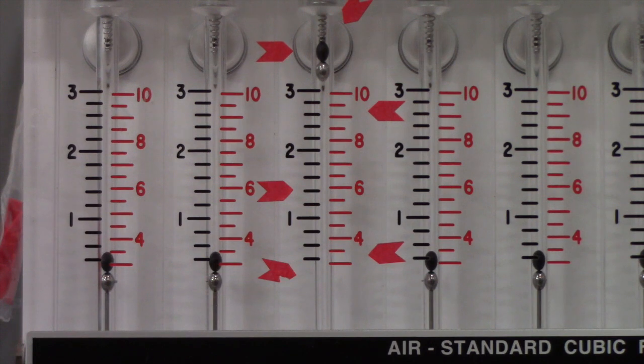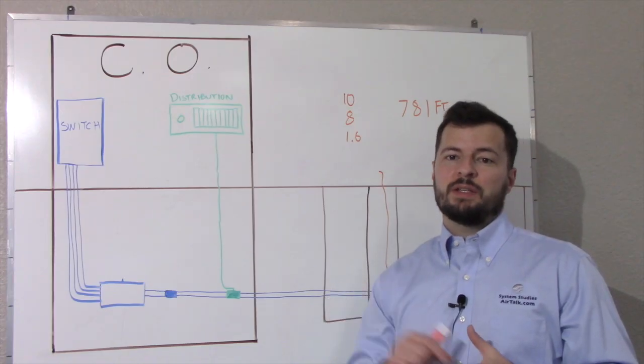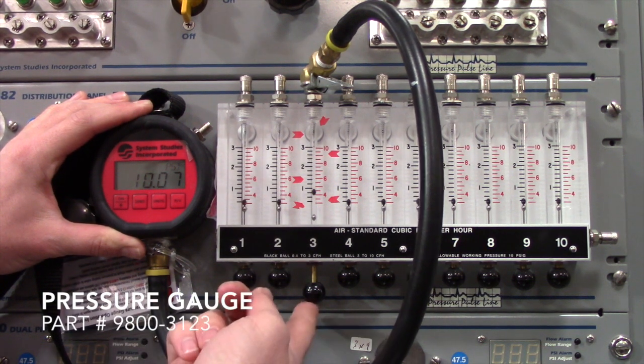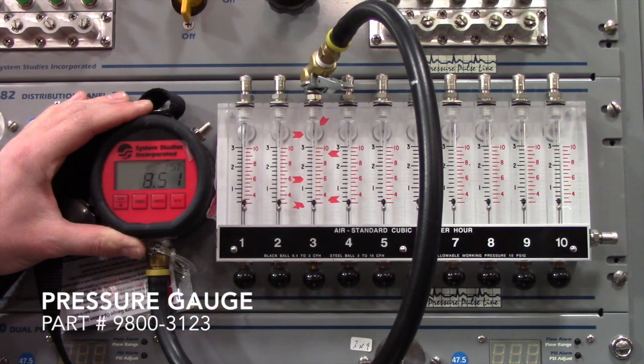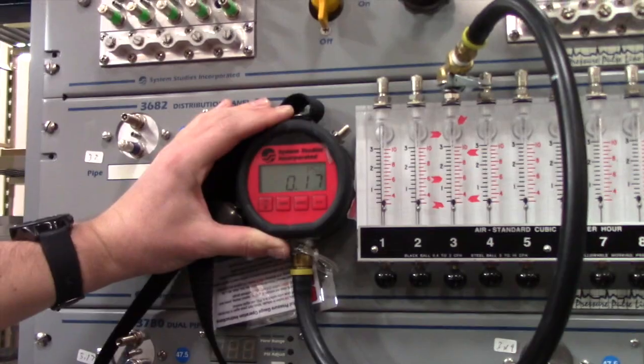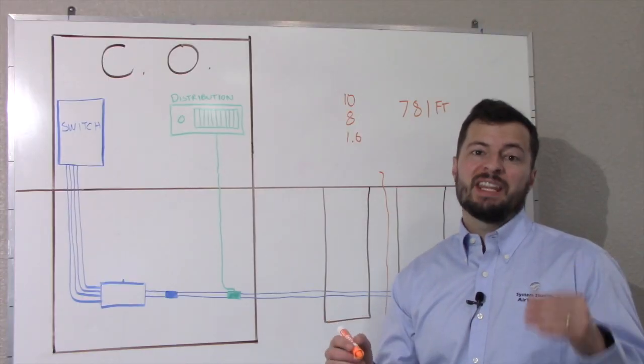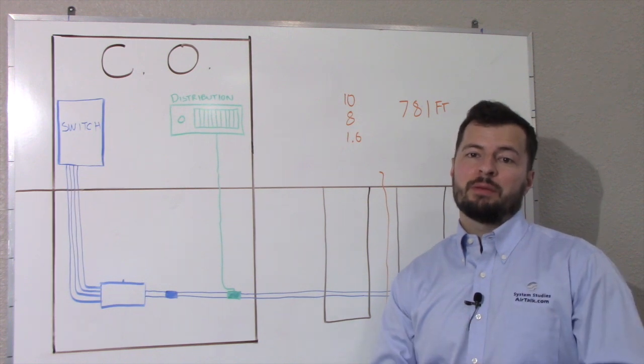You may find that with cables being removed over time, that some of these high-flowing tubes will just be ventilating the vault. This will show as a pegged cable on the flow rate. Here is a quick test for this. Put your digital pressure gauge on the valve at the top of the flow rate for that cable. Then shut off the flow to that single cable. If the pressure on that cable drops to zero in a matter of seconds, then that tube is probably disconnected somewhere. Tubes that are attached to cables will have back pressure and that will show as a much slower drop in pressure.